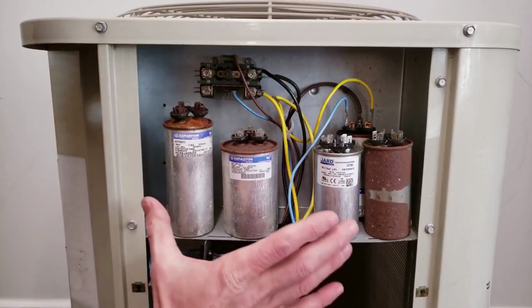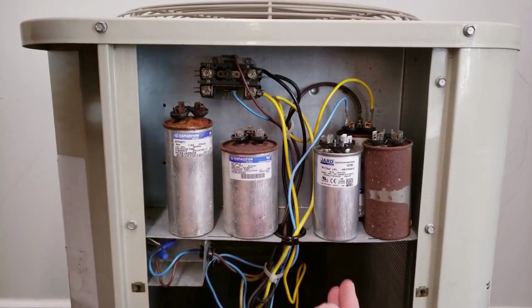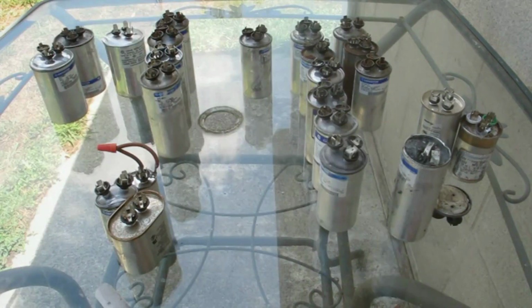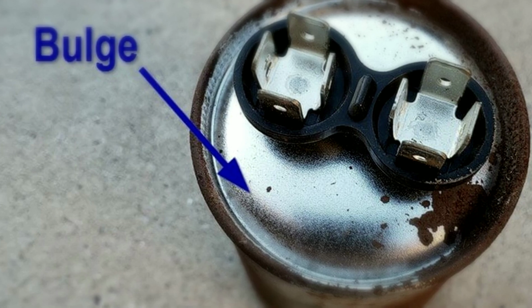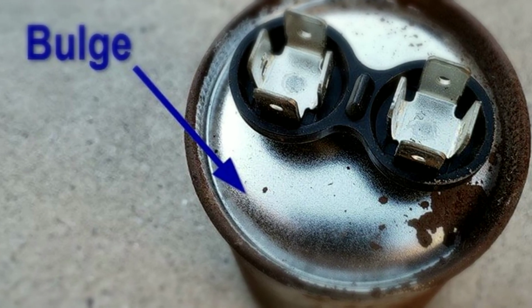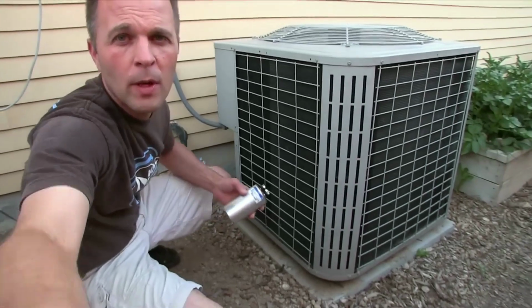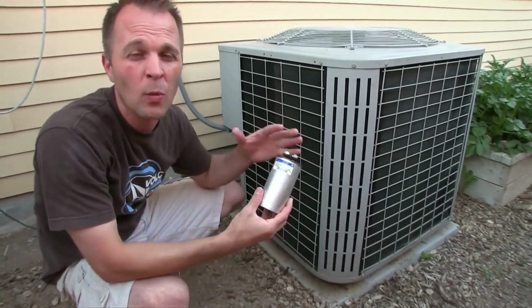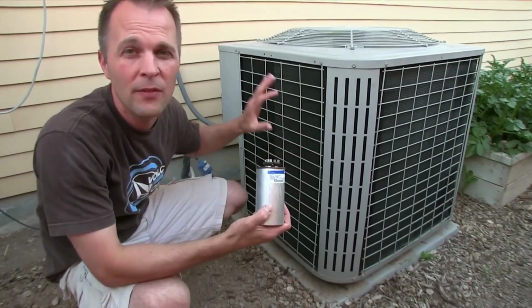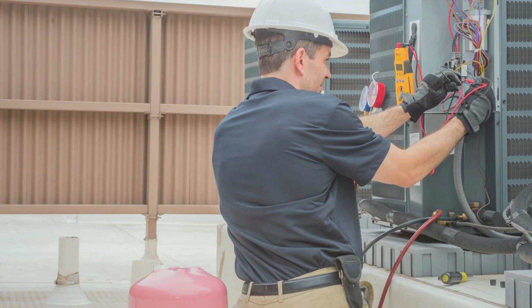You do not always need a meter. A visual inspection can be definitive. Look at the top of the capacitor. A healthy unit has a flat top. A failing or failed capacitor often shows a bulging, domed, or cracked top, sometimes with visible oil residue from internal leakage. If you see that, the diagnosis is confirmed without any measurement at all.